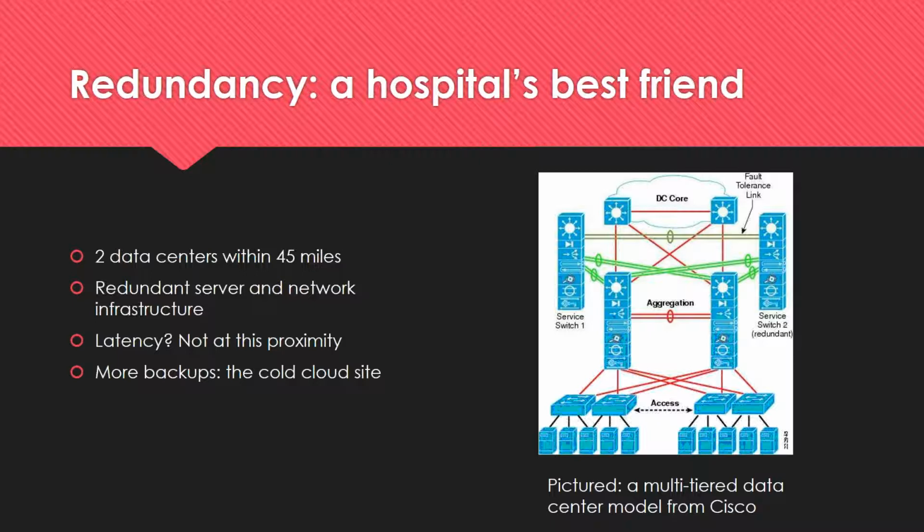Backup power generation in the form of dual UPS banks that can float power to the entire data center for a period of 20 minutes ties to dual diesel generators, each of which can run the data center independently. Maintaining a diesel tank on site of sufficient quantity is also needed. 2 external network connections from 2 separate providers allows for failure and failover of ISP when needed. All equipment in the data center should operate under a 2N design with double the amount needed to run.